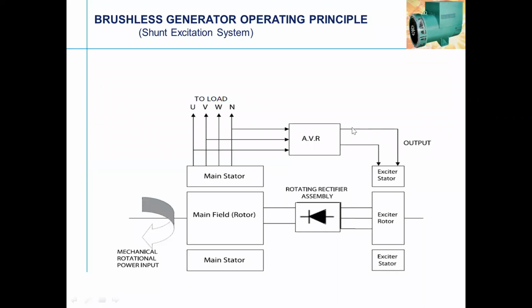For the exciter, there is again an AVR which is required to give the input. For giving the input to the AVR, there is a shunt input. This is why we call it shunt: the power input to the AVR comes from the same output winding. This is a shunt type of excitation system. This is one variant. There are some advantages and some disadvantages. Probably we can have a different session to compare shunt, RF, and PMG with load application. There is a big subject on that and we can discuss it. If you have any question, you can mail me through Mr. Prakash, and I am happy to share this information.